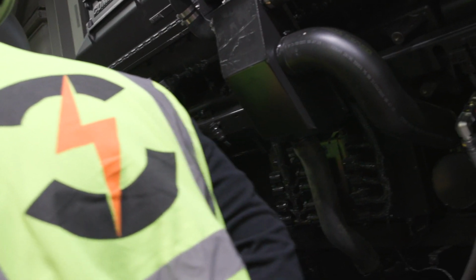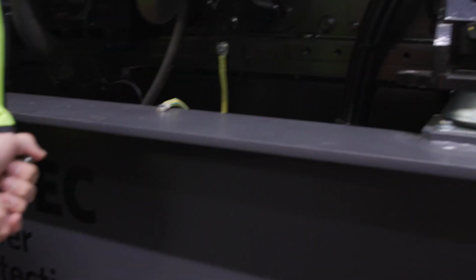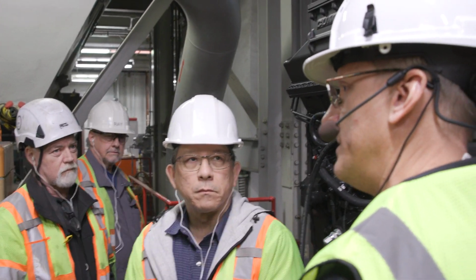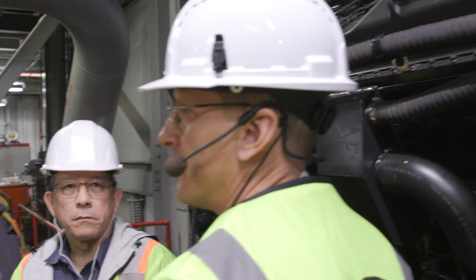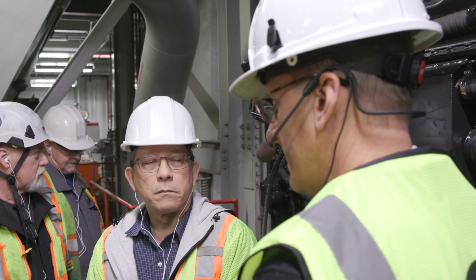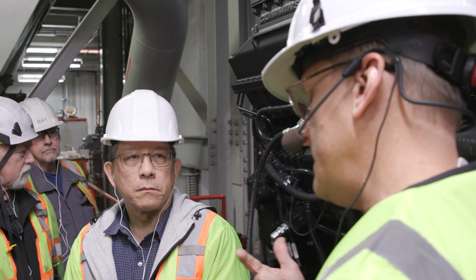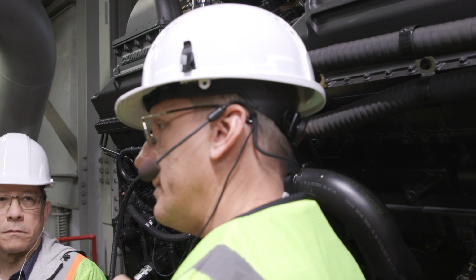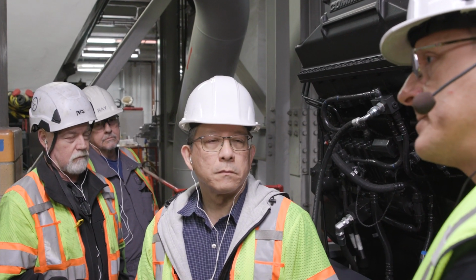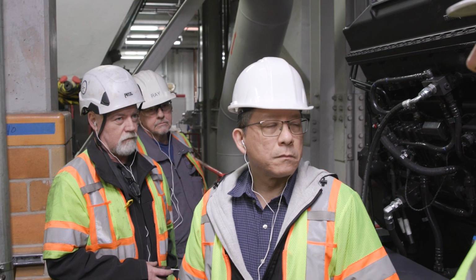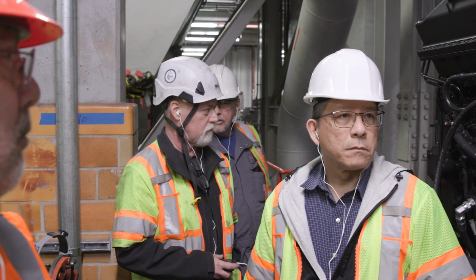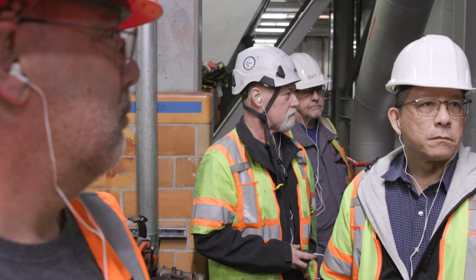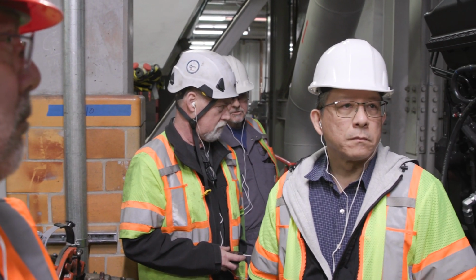Are there pyrometers on the cylinders? Sorry? Pyrometers on the cylinders measure cylinder temperature. Is there any way for us to measure that? There's no way for us to monitor that without calling Cummins in to connect to the engine and monitor through their system. But yeah, the only information we extract from the diesel is the water temp, lube oil pressure, engine running hours, and we monitor some alarms as well, some discrete alarms from the engine: high temp, low pressure, check engine light, and stop engine light.